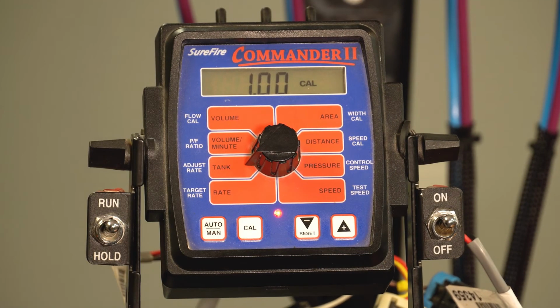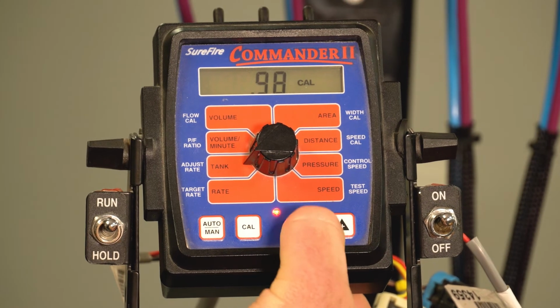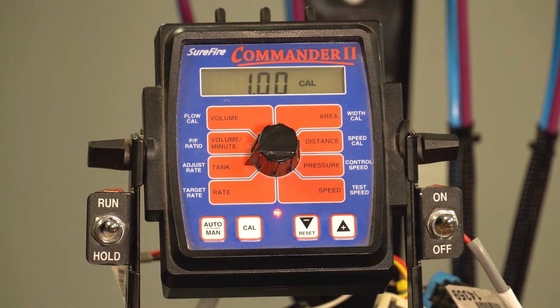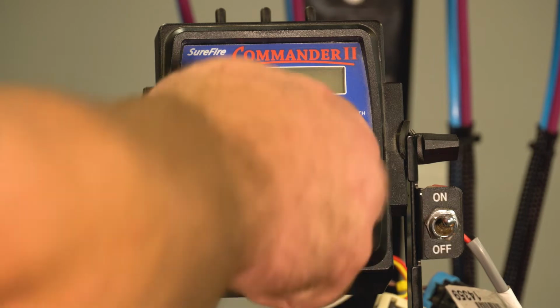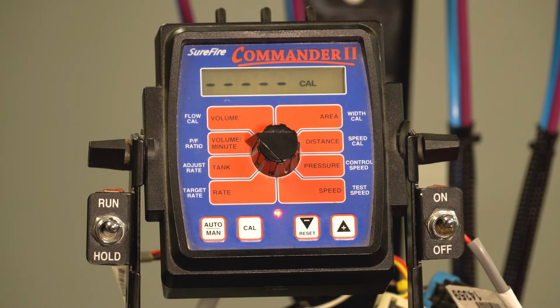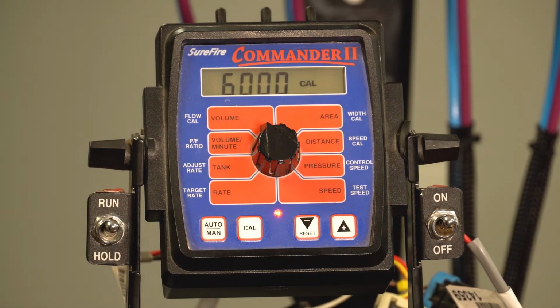Next, we go to adjust rate. And right now it is set at 1 gallon at a time. The adjust rate is where we would set the amount of rate change by pressing that plus or negative button. And again, very simple there. Most times, factory setting is at 1 gallon increments there. Next, nothing in the volume per minute or PF ratio. Then we would go to continue calibration and the startup here to the flow cal.